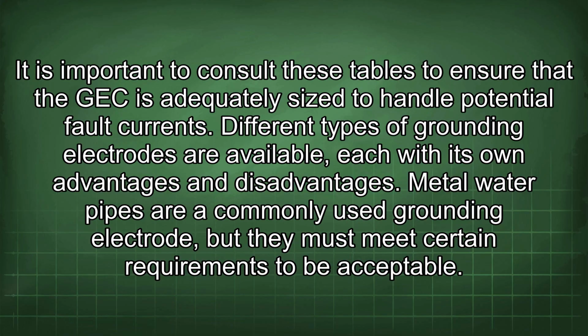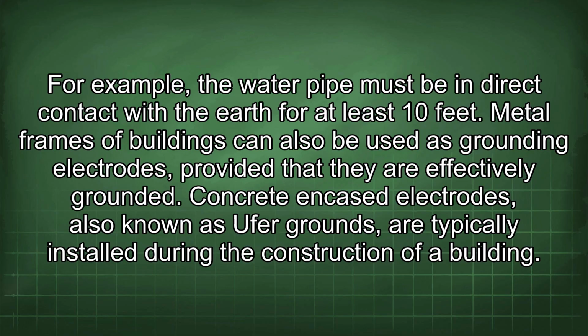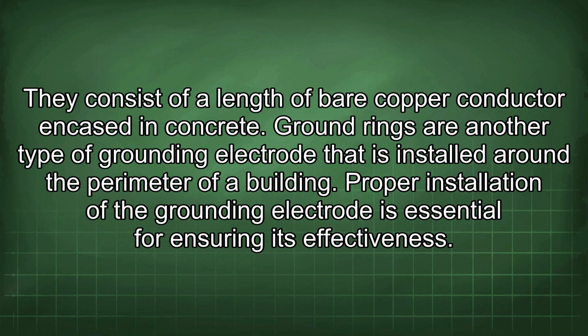Metal water pipes are a commonly used grounding electrode, but they must meet certain requirements to be acceptable. For example, the water pipe must be in direct contact with the earth for at least 10 feet. Metal frames of buildings can also be used as grounding electrodes, provided that they are effectively grounded. Concrete encased electrodes, also known as UFER grounds, are typically installed during the construction of a building. They consist of a length of bare copper conductor encased in concrete. Ground rings are another type of grounding electrode that is installed around the perimeter of a building.